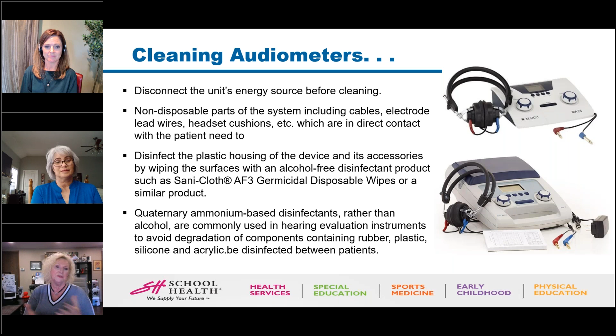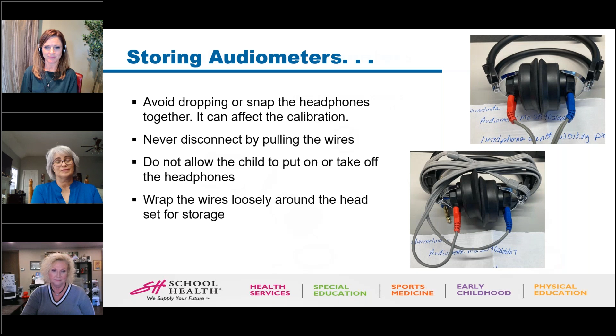When you're storing your audiometers, you want to avoid dropping or snapping the headphones together. It can affect the way they're calibrated. I have two pictures here that show the older set of headphones, where you do not want to wrap the wire around. That creates tension on your product and on your headphone wires, and they can become disengaged from the headphones or need to be replaced more frequently. So the best practice is to not wrap them around that, and never let the child take the headphones off on their own. You always want to be the person that takes them on and off the child.